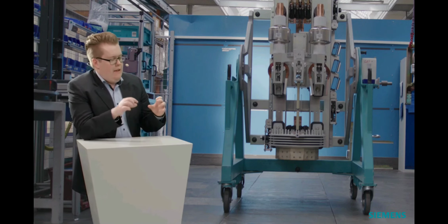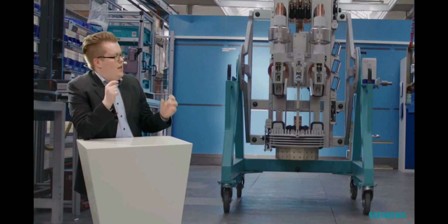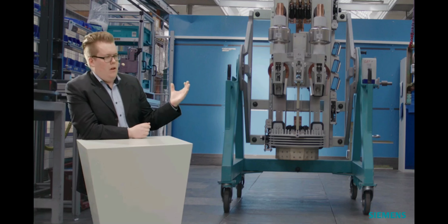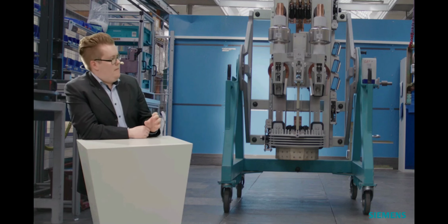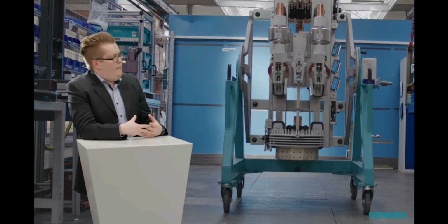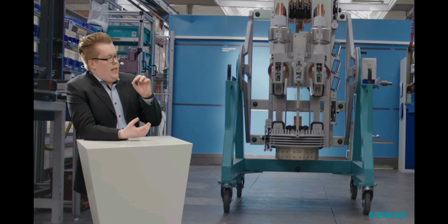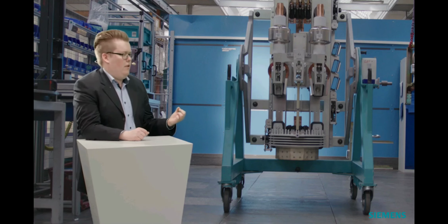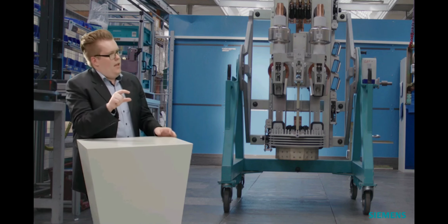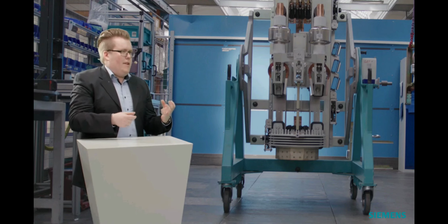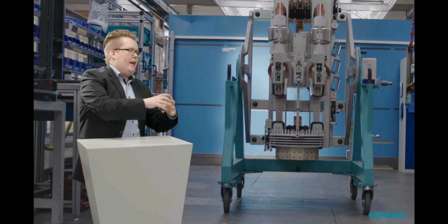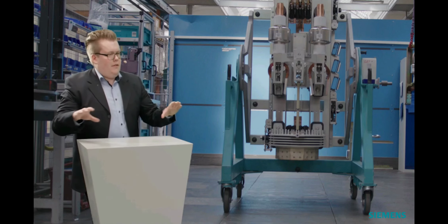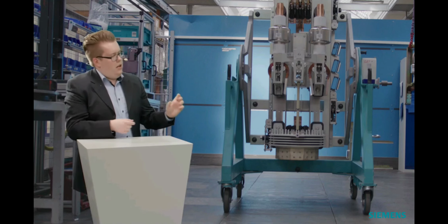So if we have a multiple generation network and we have, for example, 4 generators all having only 3 MVA of power, this will be a total power of 12 MVA. So the IEC/IEEE standard is actually not applicable for the small amount of power. This is actually the same as having one big generator for 12 MVA or 4 small generators with 3 MVA. These two powers are not covered by the standard.